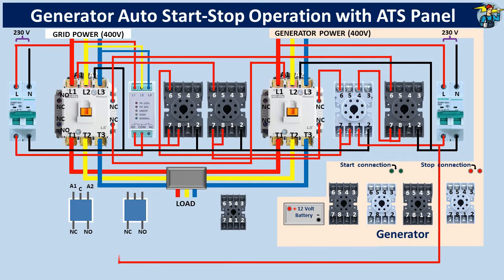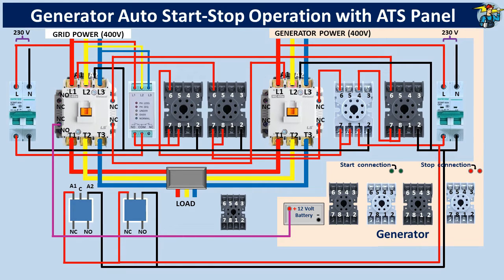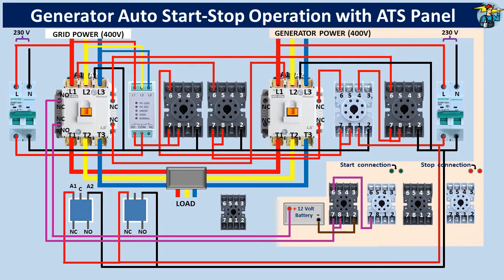Connect generator side control power to the A1 and A2 coil ends of the 5-pin SPDT relays. The line from the positive end of the battery must first pass through the normally closed auxiliary contact points of the mains contactor before connecting to port number 7 of the generator start timer. Terminal number 7 must be connected to common port number 8. Connect the negative end of the battery to port number 2 on the timer. Connect the number 6 timer output terminal to the number 7 port of the starter relay. Port number 2 is connected to the negative end. You also need to connect number 6 to number 7 of the start fail detection timer relay.